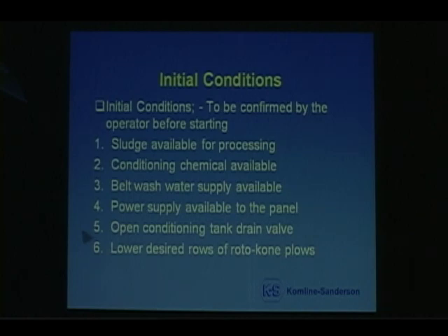Conditions to be confirmed by the operator before starting. Make sure all your sludge is available and all the valves are open. You've got a lot of pneumatic valves that are put in place, so make sure all the valves are open. Same thing with the conditioning chemical, your polymer. Make sure all the valves are open.